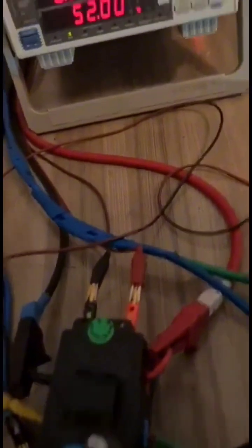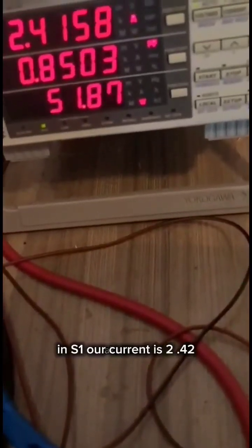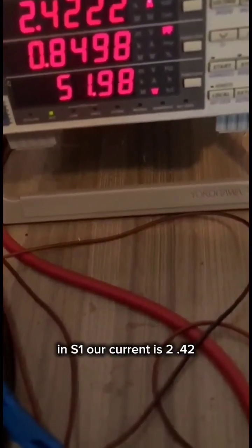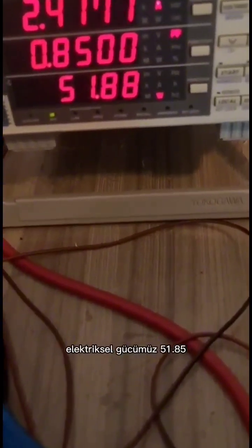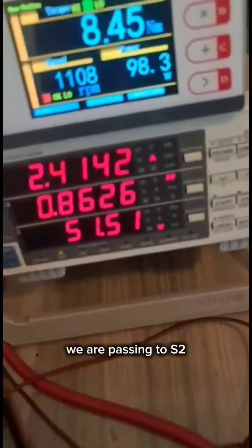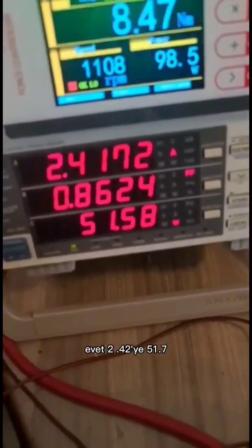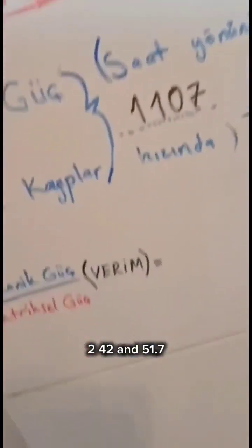Meanwhile, we are in S1. In S1, our current is 2.42. Our electrical power is 51.85. We are passing to S2. Yes, for S2, 2.42 and 51.7. Now we turn off our motor.